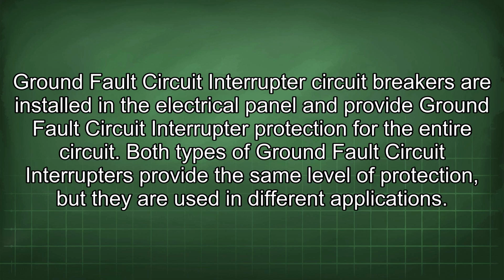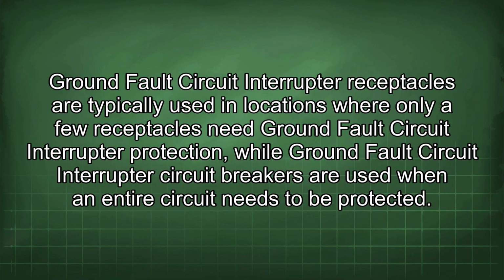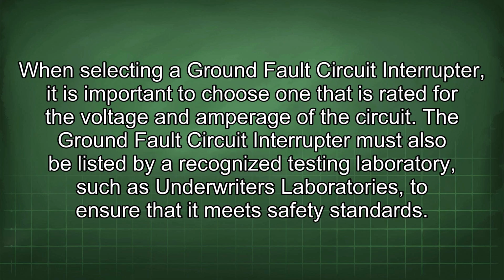Both types of ground fault circuit interrupters provide the same level of protection, but they are used in different applications. Ground fault circuit interrupter receptacles are typically used in locations where only a few receptacles need ground fault circuit interrupter protection, while ground fault circuit interrupter circuit breakers are used when an entire circuit needs to be protected. When selecting a ground fault circuit interrupter, it is important to choose one that is rated for the voltage and amperage of the circuit. The ground fault circuit interrupter must also be listed by a recognized testing laboratory such as Underwriters Laboratories to ensure that it meets safety standards.